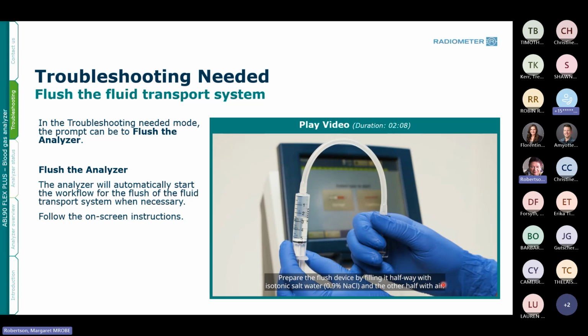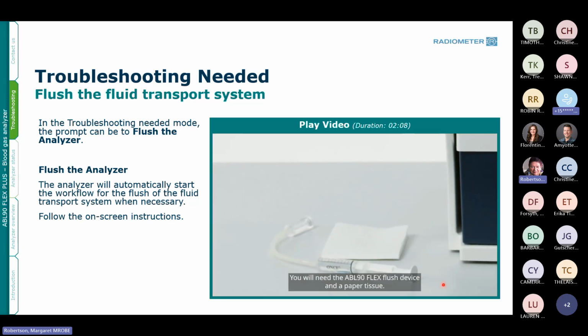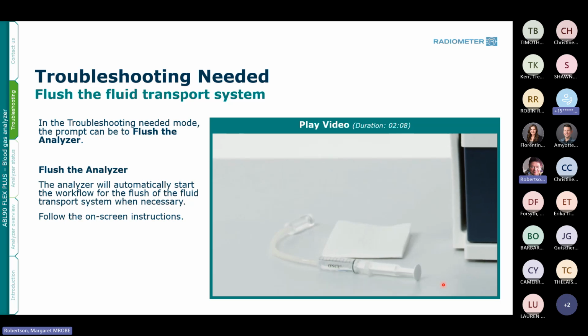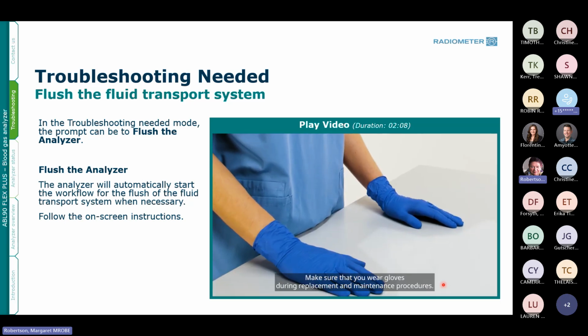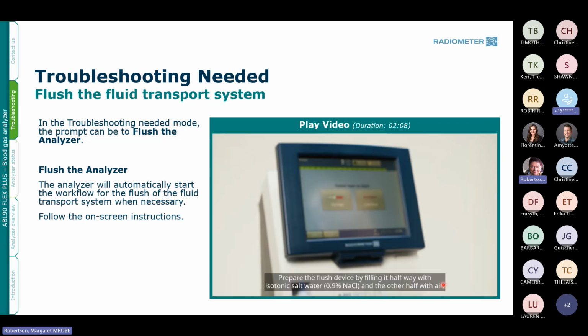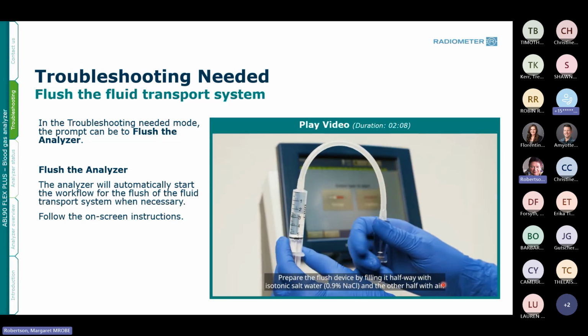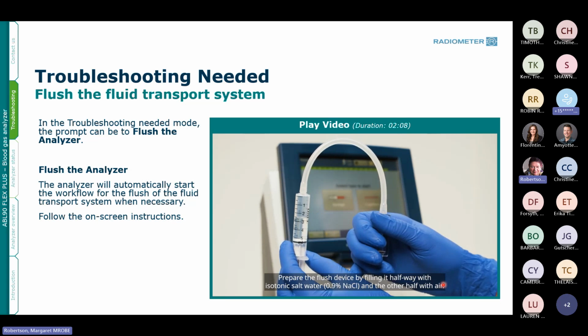The next step is having to flush the analyzer. This only happens if the analyzer gets a clot that it can't remove on its own. The analyzer will try twice to flush the clot before it comes up and says, hey, I need some help here. It will bring up a message that tells you what it needs to do. You will need the ABL90 Flex Flush device and a paper tissue. Make sure you wear gloves during replacement and maintenance procedures. Prepare the flush device by filling it halfway with isotonic salt water, 0.9% NaCl, and the other half with air.